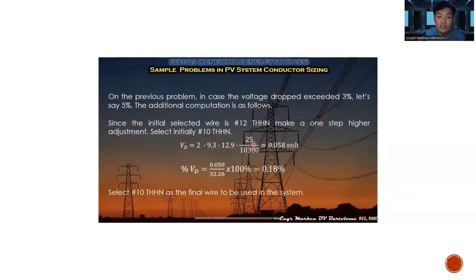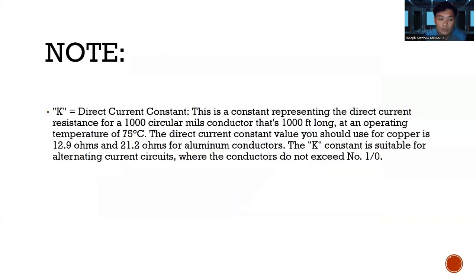So, on the previous problem, in case the voltage drop exceeded 3%, let's say 5%, the additional computation is as follows. Since the initial selected wire is number 12 THHN, make a one-step higher adjustment. Select initially number 10 THHN. So, formula ulit tayo. VD is equals to 2 times 9.3 times 12.9 times 25 over 10,380 is equals to 0.058 volts. So, sa percentage naman tayo. VD is equals to 0.058 over 32.26 times 100% is equals to 0.18%. Select number 10 THHN as the final wire to be used in the system. So THHN na gagamitin natin doon.